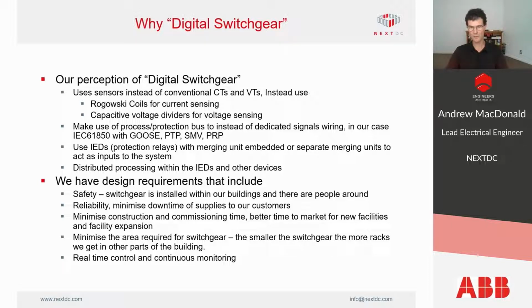We want to minimise the construction and commissioning time. That gives us a better time to market for new facilities when we build them, and for facility expansion when customers decide that they want additional space or new customers want to move into an existing facility. We want to minimise the area required for our switchgear. The smaller the switchgear, the more racks we can have in other parts of the building, and we get paid for our racks, which makes them far more valuable than switchgear for us. The other advantage is we want real-time control and continuous monitoring of our switchgear, so if we have a fault, we can rectify it quickly.